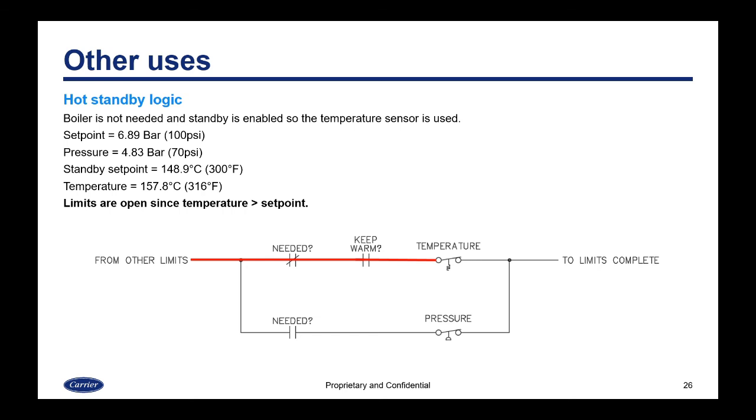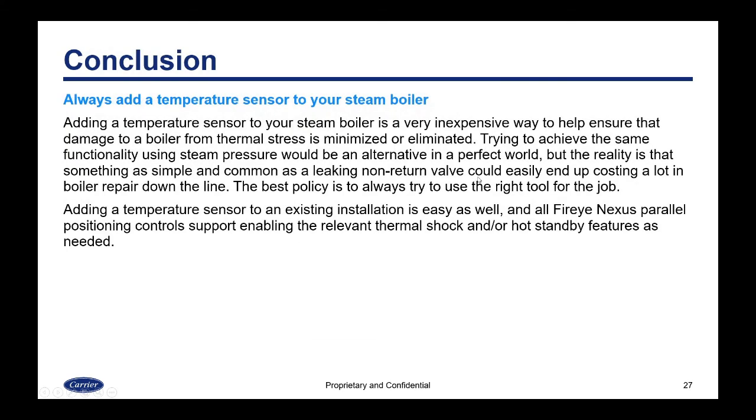Adding a temperature sensor to your steam boiler is a very inexpensive way to help ensure that damage from thermal stress is minimized or eliminated. Trying to achieve the same functionality using just steam pressure would be an alternative in a perfect world, but something as simple and common as a leaking non-return valve can easily end up costing a lot in boiler repair. The best policy is always to use the right tool for the job — in this case, the temperature sensor. All Fireye Nexus parallel positioning controls support enabling the relevant thermal shock or hot standby features. The best time to specify the temperature transmitter is during the original install, before water is in the boiler.